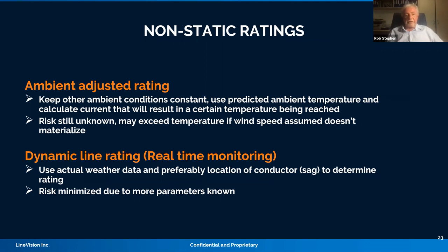If you now look at non-static ratings, and I've determined to call it non-static rather than dynamic, there are many different kinds. The one that you're looking at here is really an ambient adjusted rating. What you do there is, if you've got a deterministic rating, and say you're assuming 40 degrees C ambient and a certain wind and certain solar radiation conditions, and you know that the weather tomorrow will give you 20 degrees ambient, you plug 20 degrees in with the wind speed and solar radiation, and you just calculate the current which will result in your design temperature being reached with that ambient value.